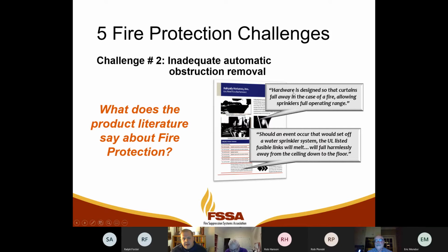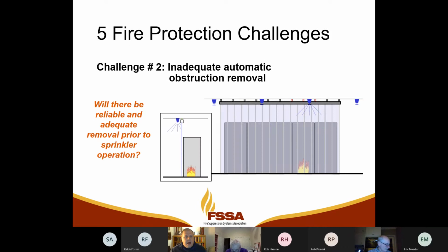Now they'll say, and this is one of the cut sheets out there, "Hardware is designed so that curtains fall away in the case of a fire, allowing sprinklers full operating range." Another quote: "Should an event occur that would set off a water sprinkler system, the UL listed fusible links will melt and fall harmlessly away from the ceiling down to the floor." They used language that made us feel good, like UL listed and allow the sprinklers full operating range. But the problem is, in that case, you've got to have a big fire to melt all those links and get those things to start falling down, which is not good in a data center.